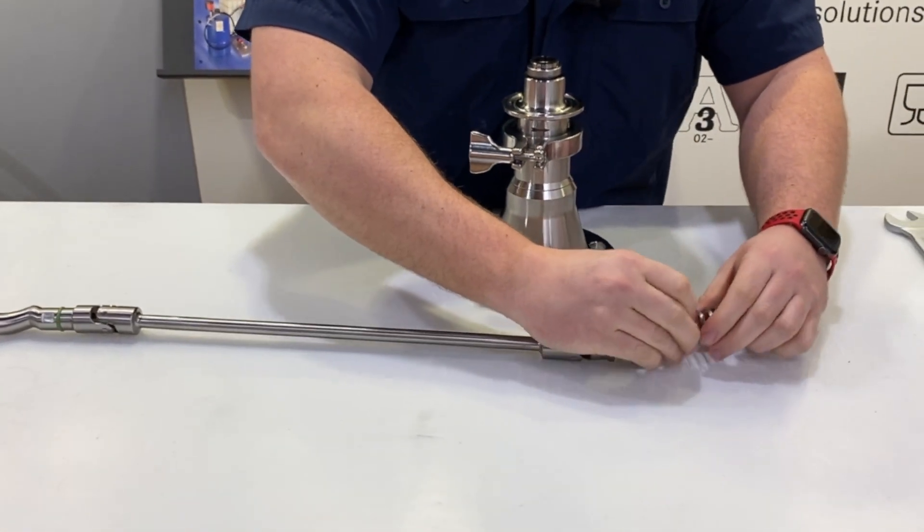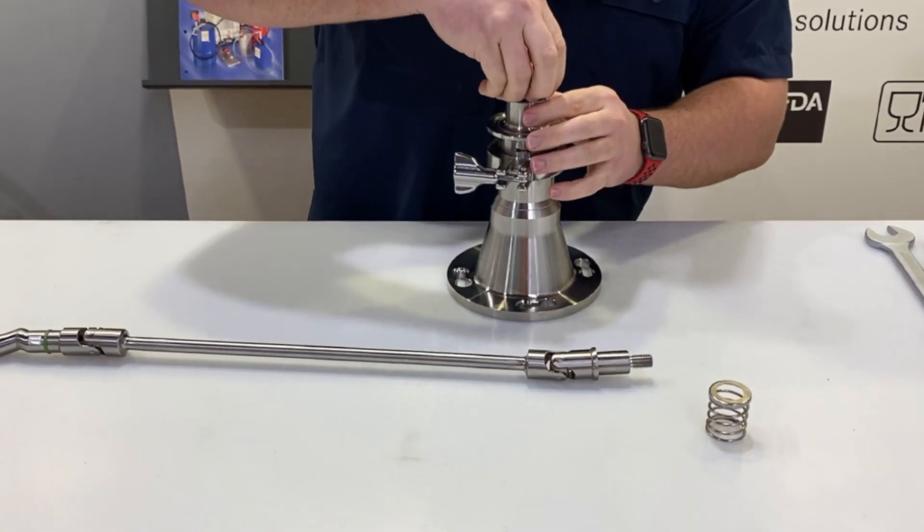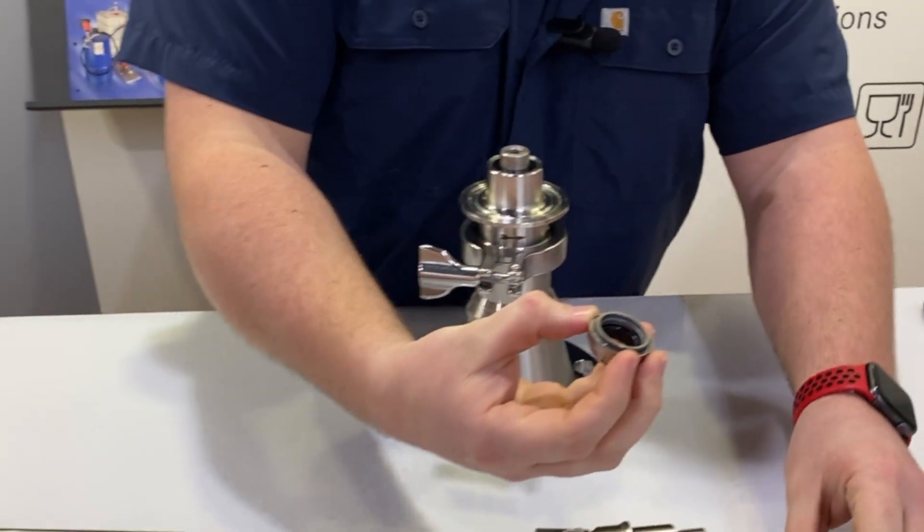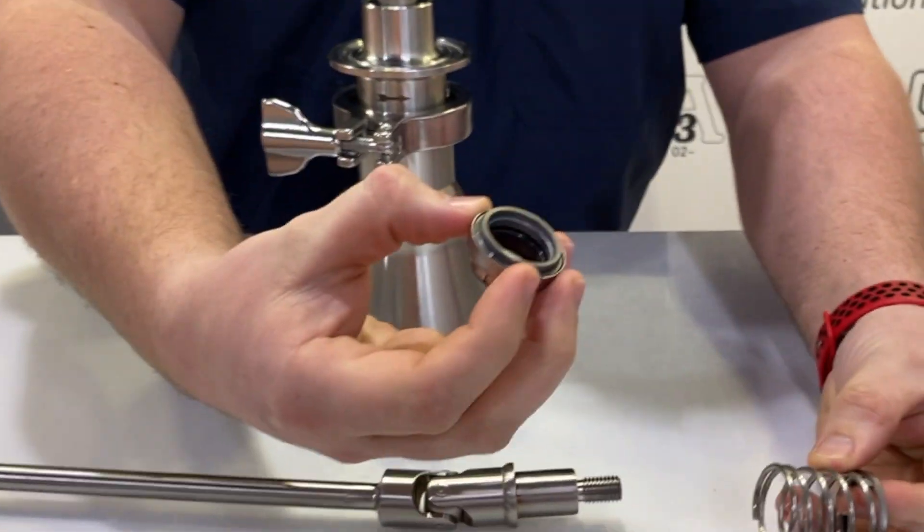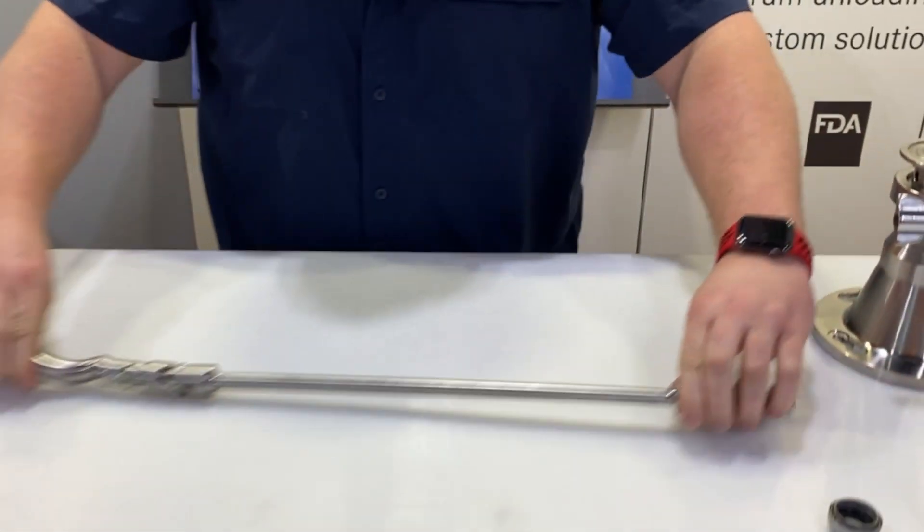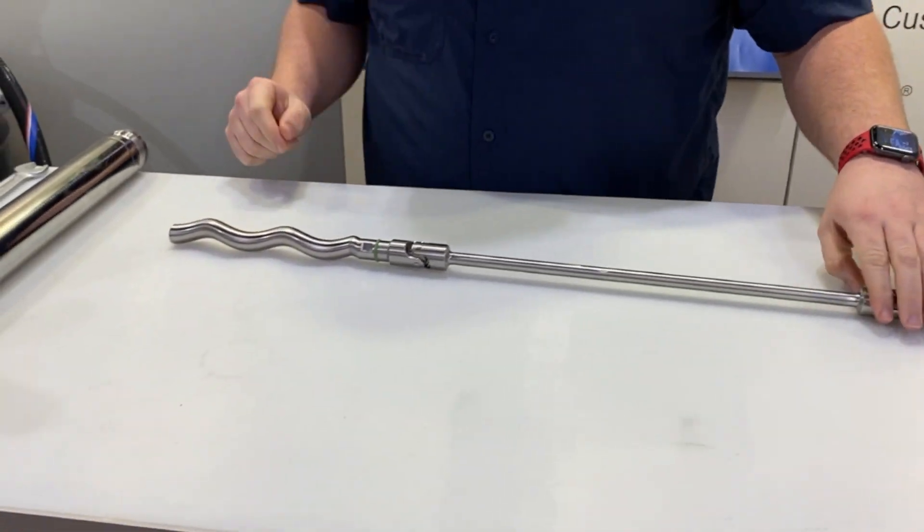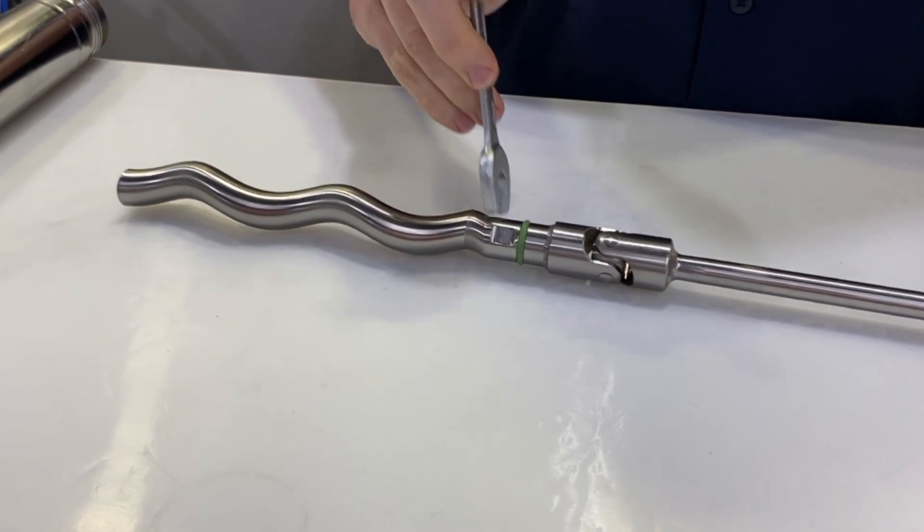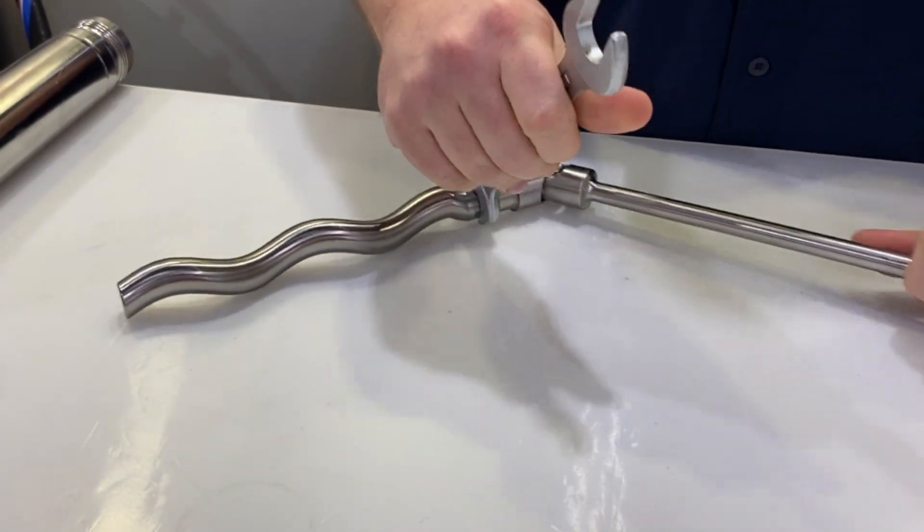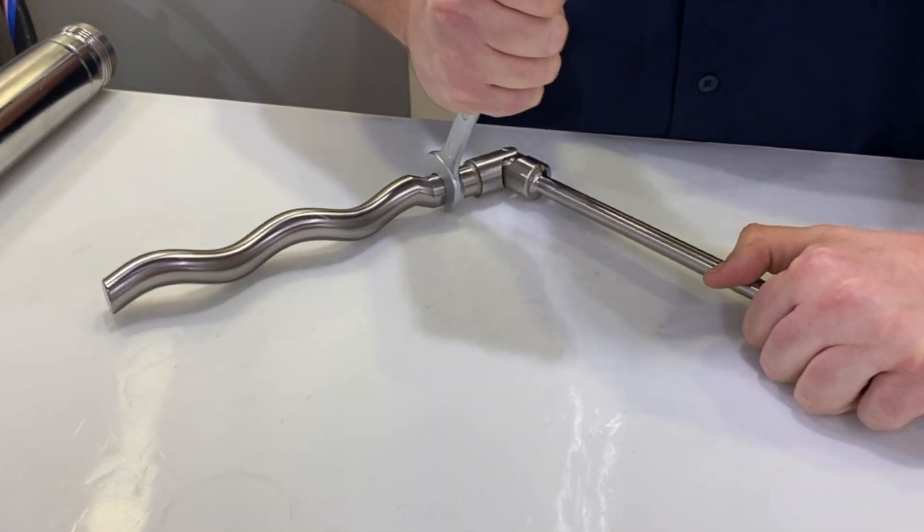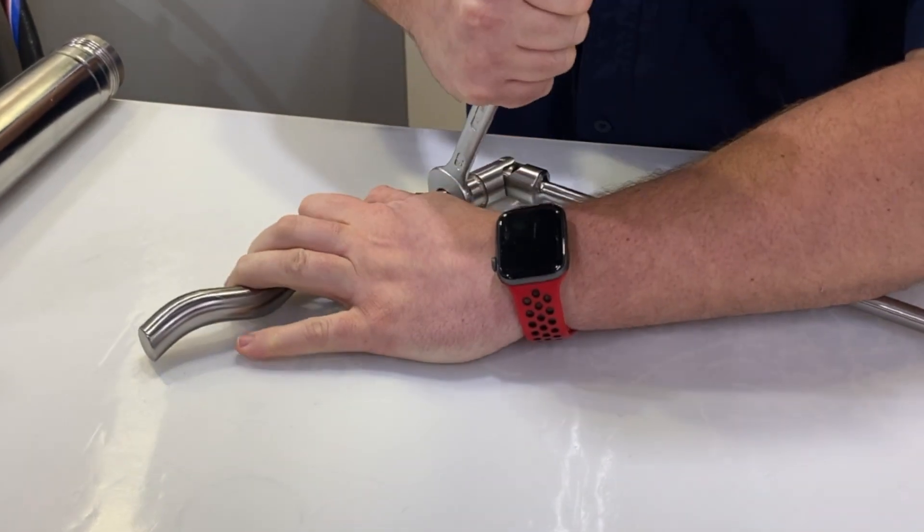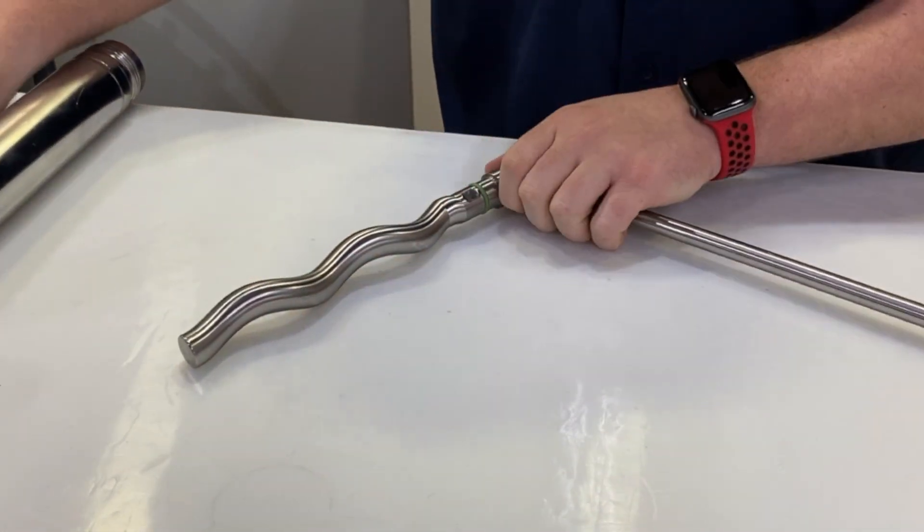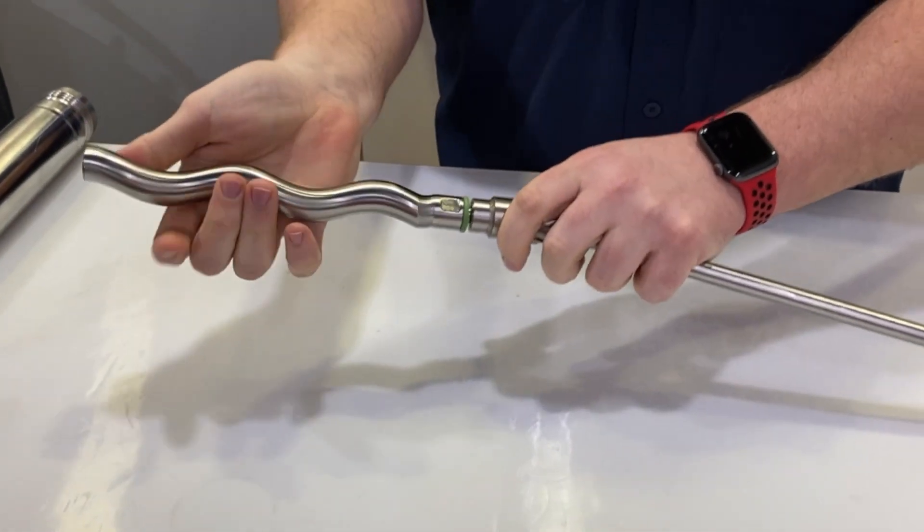Along with the shaft, you will get the mechanical seal spring and the rotating face of the mechanical seal. We will remove the rotor from the bottom of the shaft. This is done using an 18 millimeter wrench. Break that loose and then thread the rotor off.